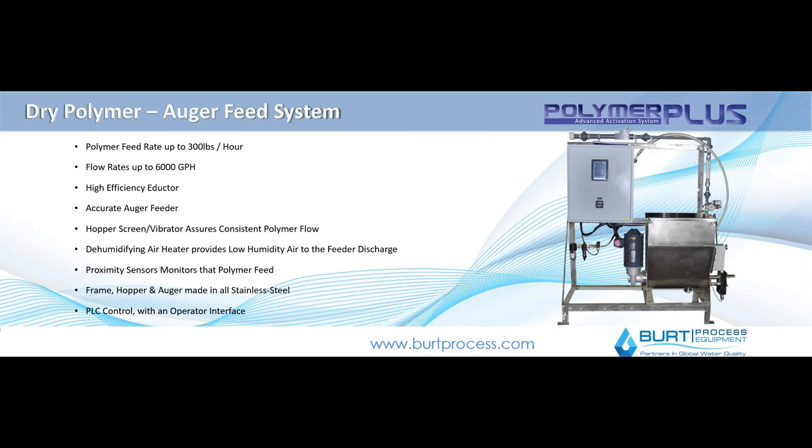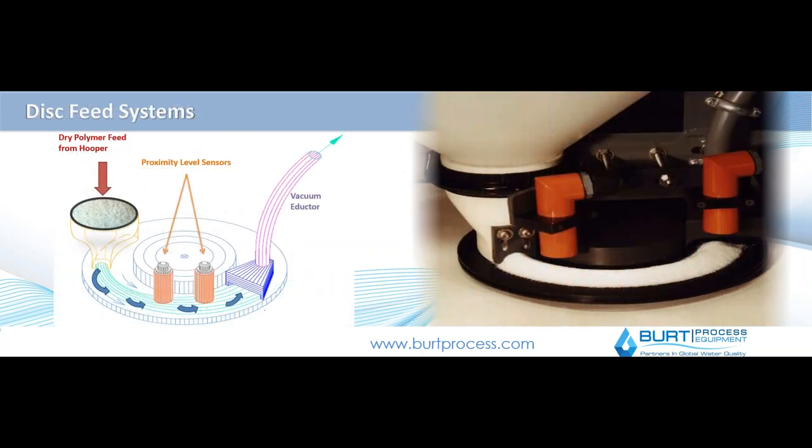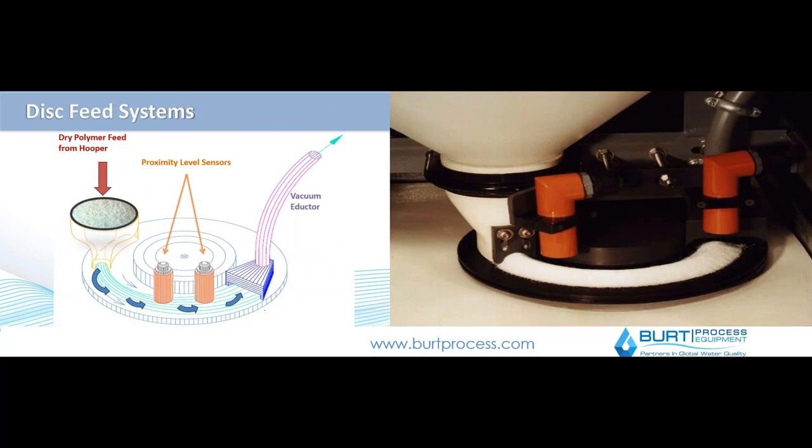Still, it's a very good device when you need a lot of bulk polymer injection. Another option is a disk feeder type device — a disk feeder essentially has a vacuum type device that sucks the polymer off of basically a disk, where the polymer is first placed, and then transferred by vacuum suction into your actual blending tank for use. You can see a close-up here of how that operates. Dry polymer feed is dropped on there, typically based on a level-based measurement, with proximity sensors that measure the polymer, and then a vacuum eductor transfers the polymer from that disk-based device into your blending tank.